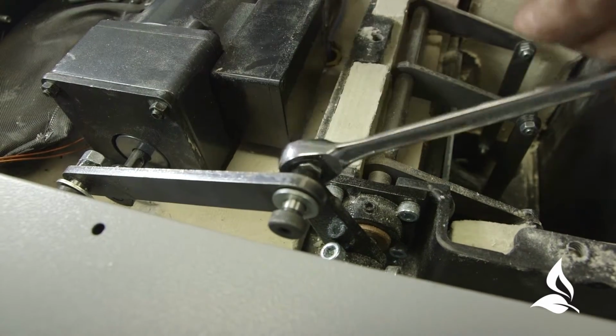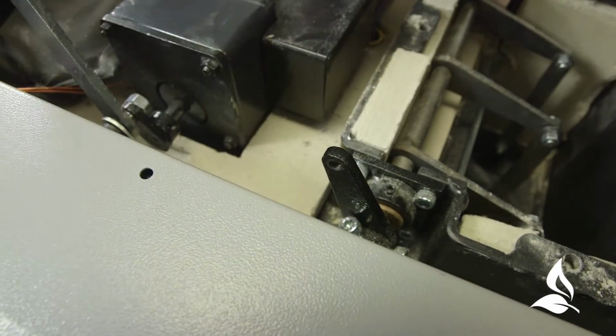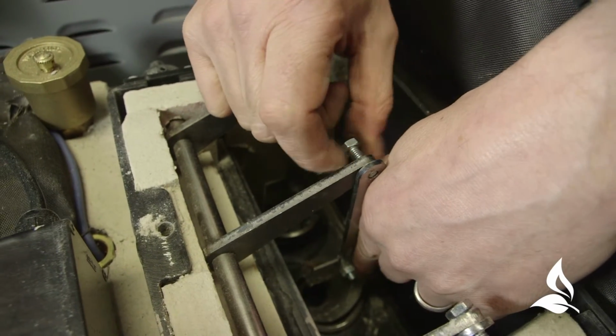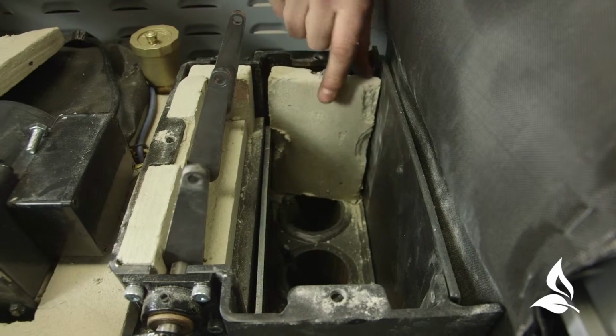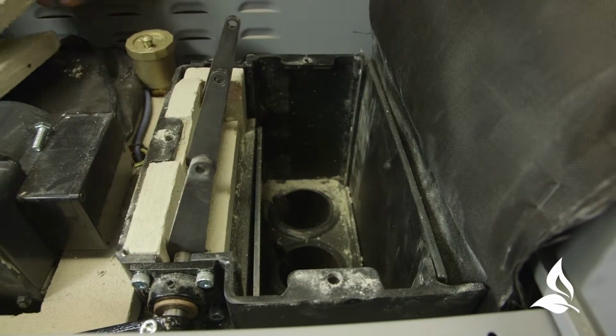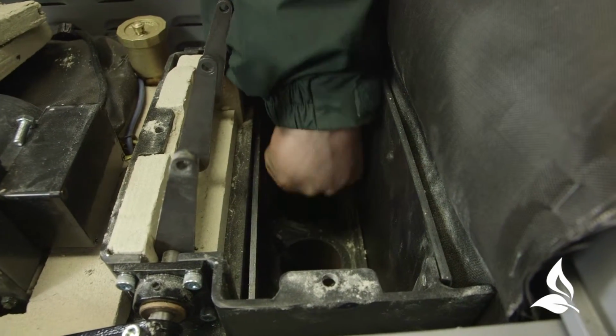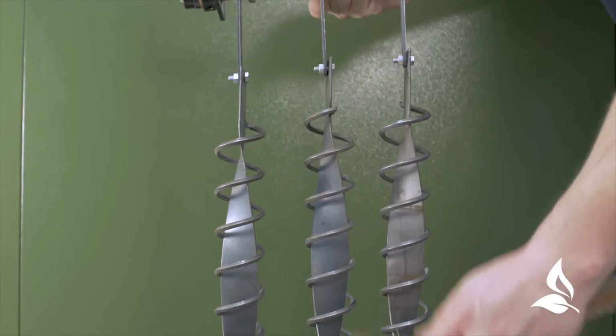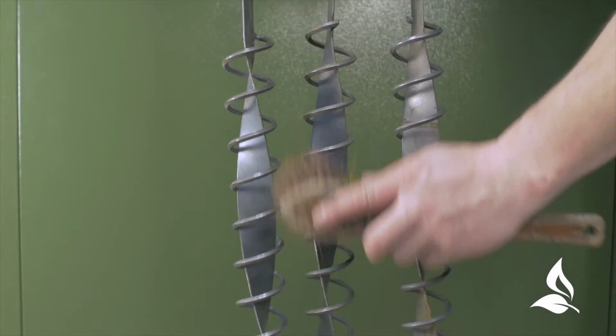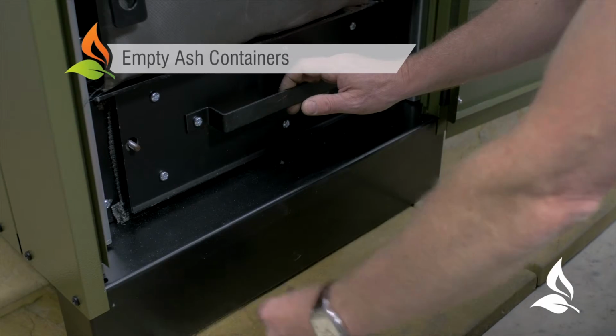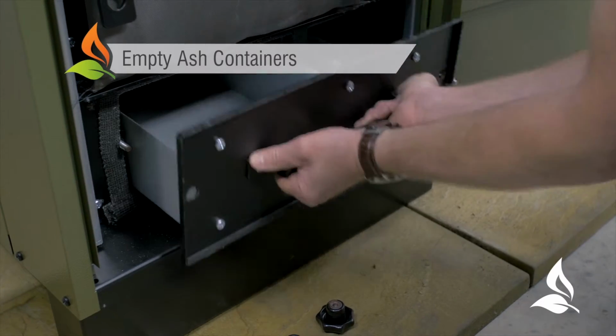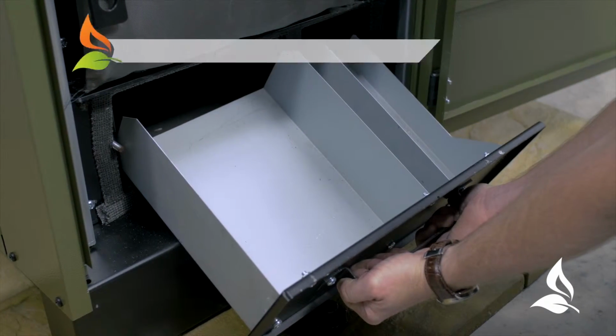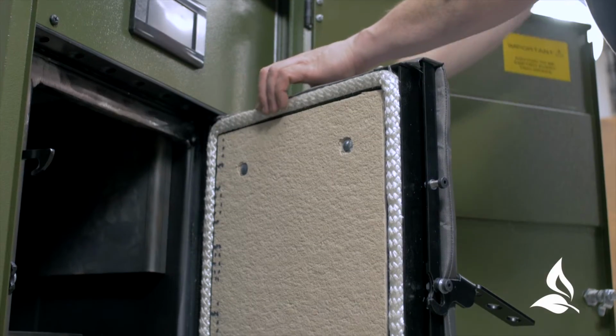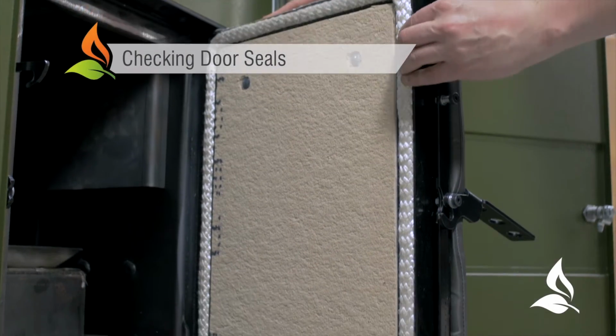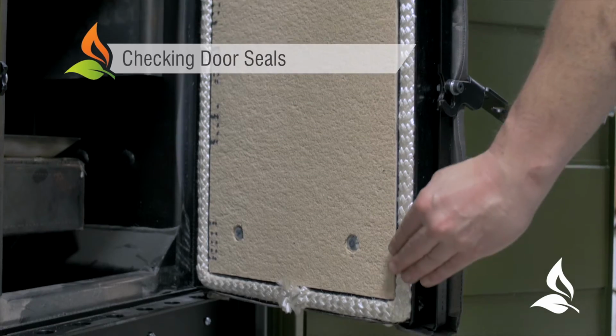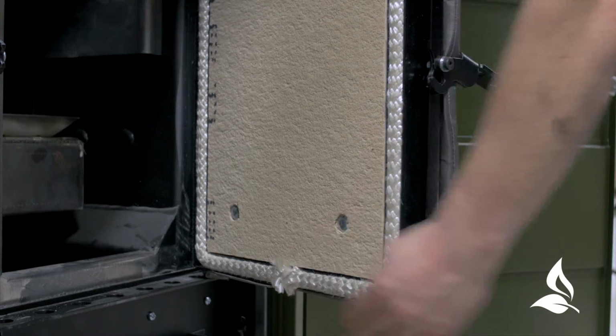Uncouple the crank arm first, then remove the bolts from before and after the pivot plates, then withdraw the turbulators from the tubes. Empty ash containers. Ensure the ash boxes are repositioned correctly. Check the sealing rope and tape on the lower ash pan door and main combustion chamber door to ensure that it maintains a good seal. Replace if necessary.